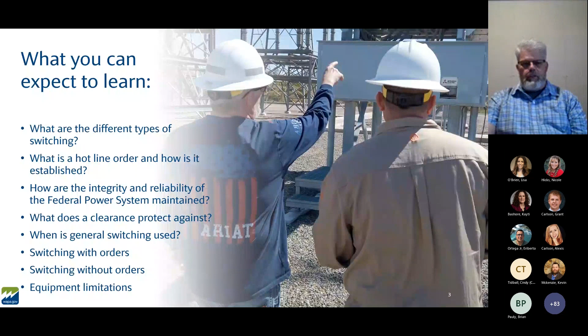Anytime a person is switching, it doesn't matter if it's in a power plant, a substation, in the dispatch center with a system operator switching on SCADA, or if it's an electrician or lineman switching in a substation. Anytime you're switching, you have to follow the 6 basic steps of switching. The key is that you have to complete all 6 of these steps in order to get one step of switching completed.